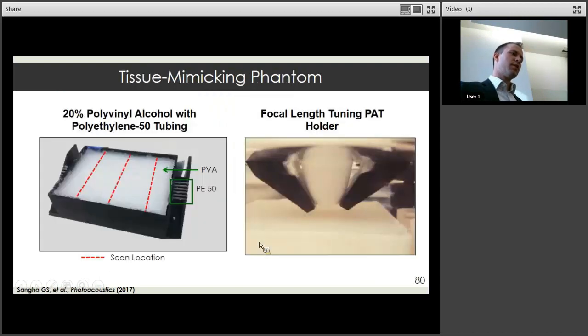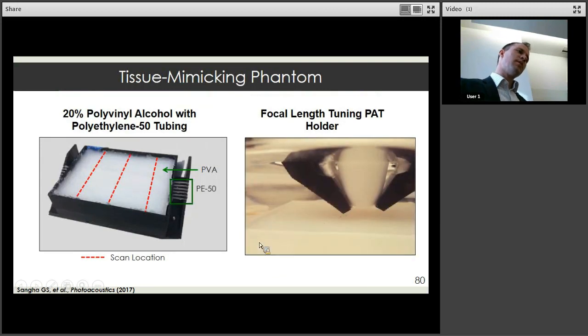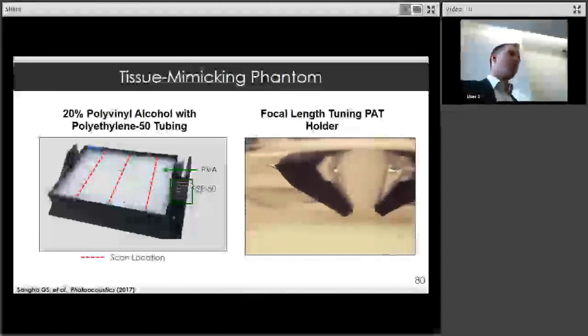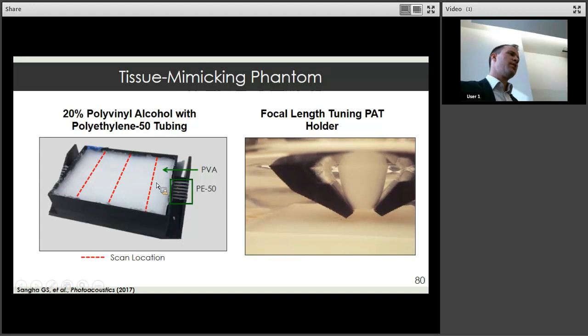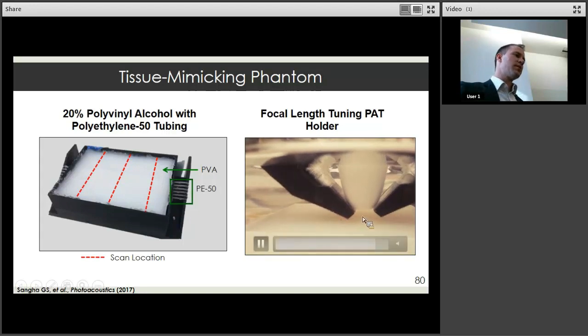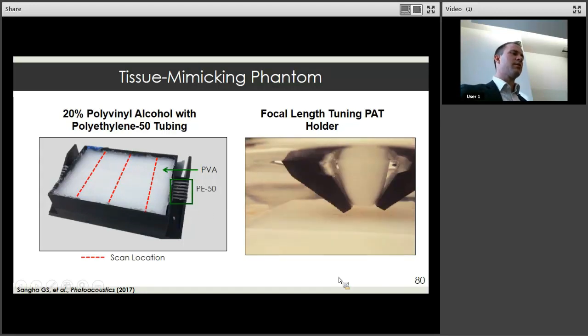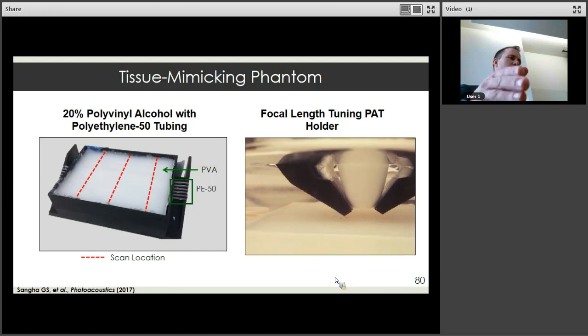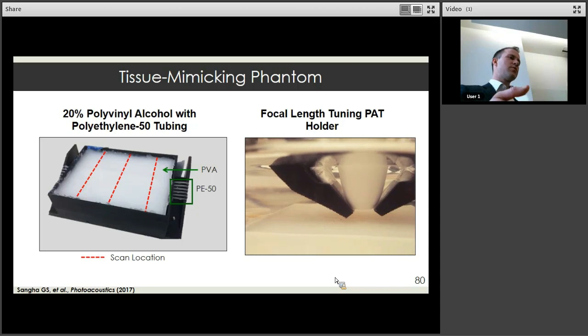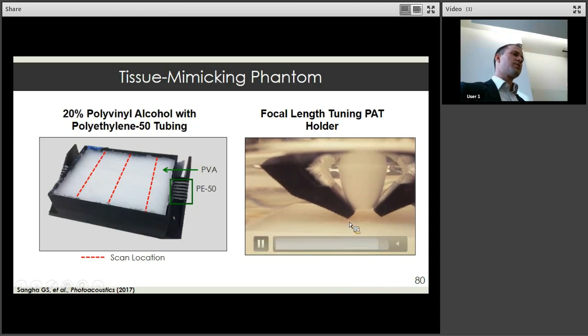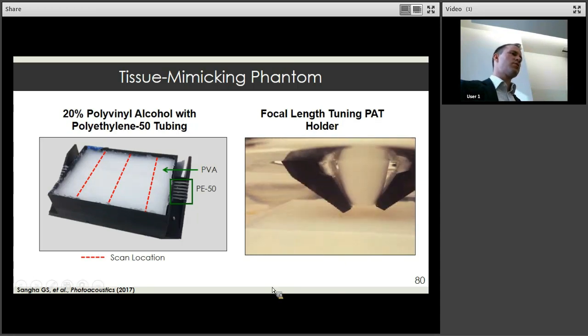But with rodents, they're actually pretty small, so a lot of times we want to do fairly shallow imaging. But we did this first with a PVA, polyvinyl alcohol, phantom, with embedded polyethylene 50 (PE50) tubing at different depths. You can see the fiber optic cables here changing in orientation. So that, again, is going from a deeper imaging setup. Now, if we want to go more shallow, we change the orientation a little bit at an angle, so now we can deliver light closer up towards the transducer surface. But we can also influence the offset angle here as well with this approach.